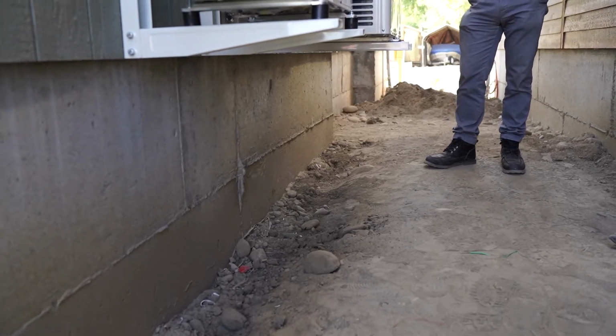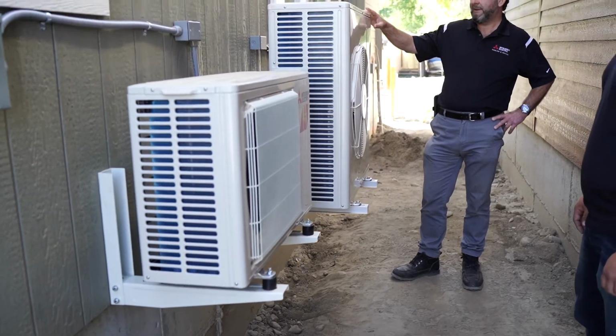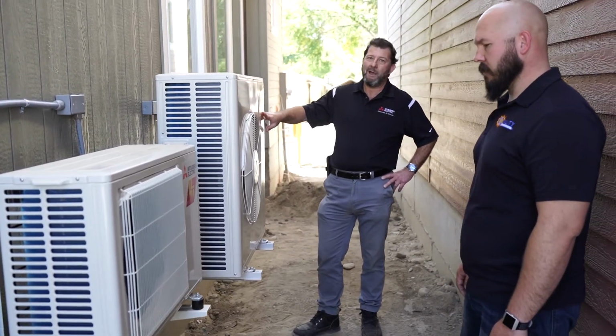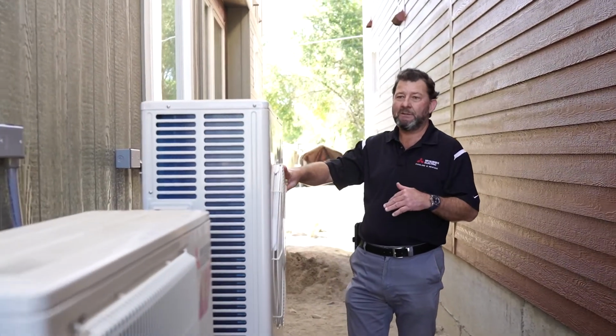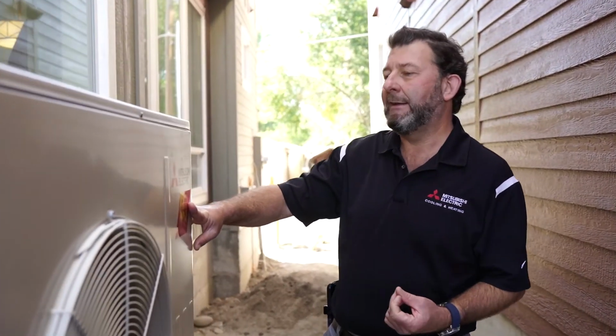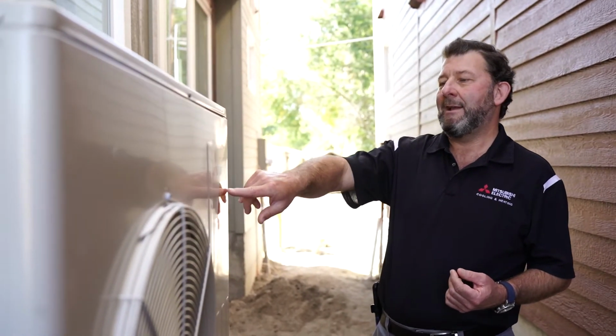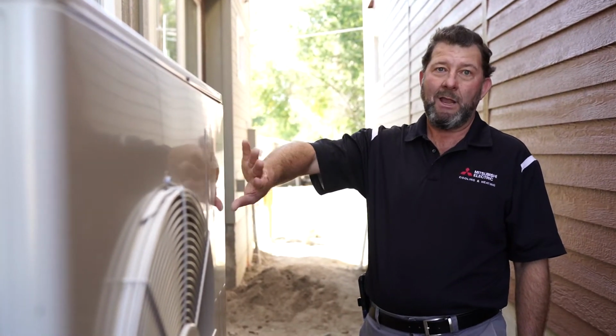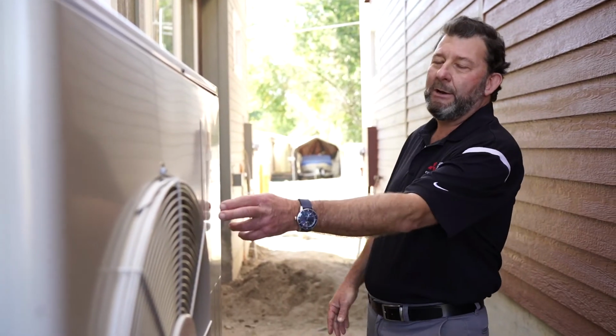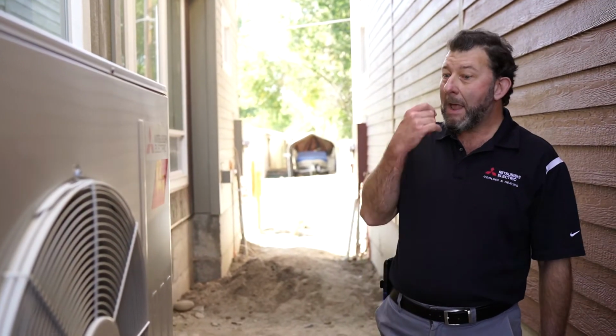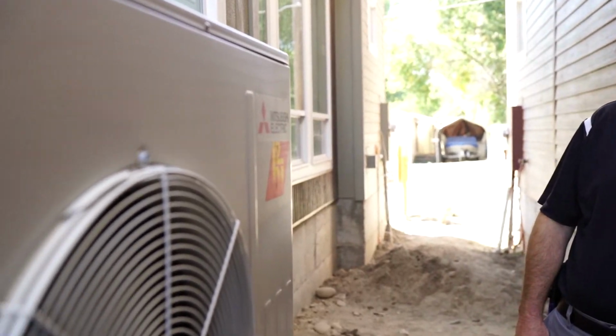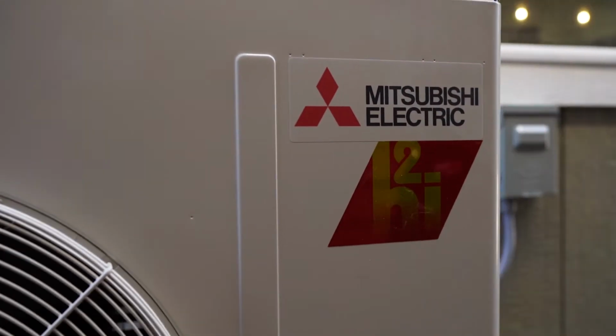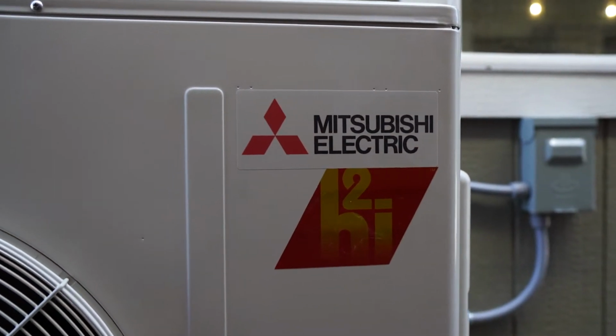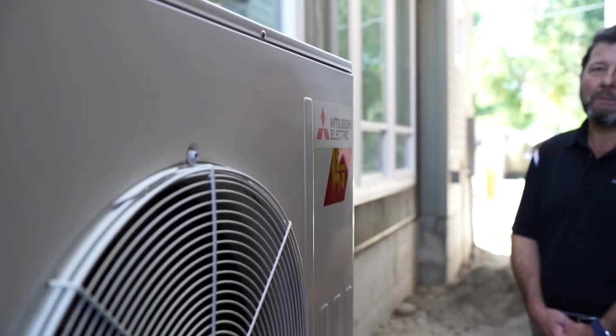One other note on these variable capacity heat pumps: these are cold climate systems, designed to operate in areas below about 32 degrees and still be energy efficient. That's one of the new areas in variable capacity heat pumps, and there's a lot of need for training in the marketplace on how to design and install cold climate heat pump systems well. This logo indicates they're cold climate capable systems, and when you do that you have to make a few small differences—one is making sure you put the outdoor units above the snow level. It's surprising how many parts of the country we see where installers don't get them higher than the snow, and that can damage or destroy the equipment pretty easily.